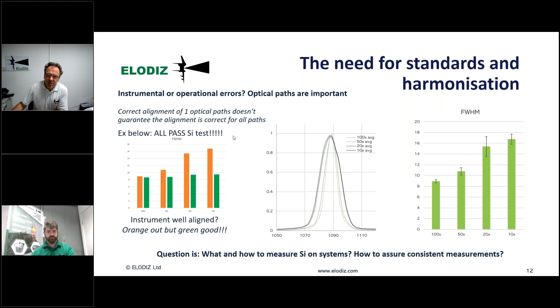There are other ways to test and verify the capability of the system, and that has been addressed by the proposal. Another thing that has been deeply studied in the project is what type of peak fitting needs to be done for every single step of the calibrations. Many Raman manufacturers take neon lamps and analyze the neon peaks, and the majority of people take the peak maximum. That is unfortunately incorrect, because it introduces some deviation depending on the optical setup, and then it can introduce further deviation on the Raman spectrum.